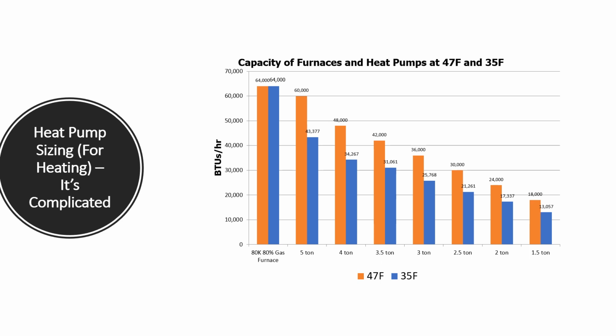Let's look at a 3-ton heat pump. At 47 degrees, one of the AHRI rating points, sure enough, you get your 3 tons of heating. But by the time we get down to 35, we're actually closer to a 2-ton equipment. We also have to take into account the capacity of the heat pump at various outdoor temperatures for sizing.